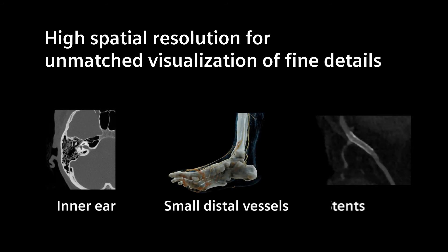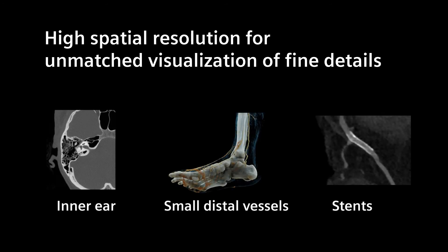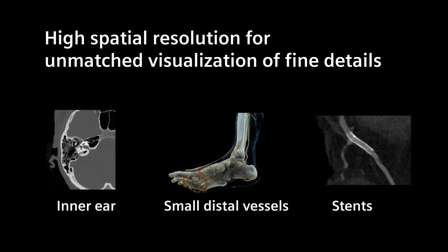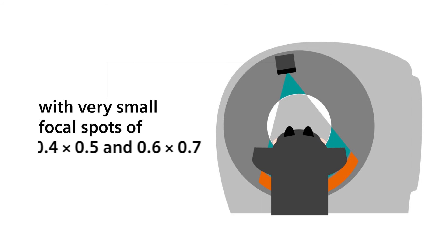For unmatched visualization of fine details, for example in inner ear imaging and CT angiography, you need high spatial resolution. That's why we designed our Vectron X-ray tube to provide very small focal spots independent of the KV, current settings, and scan duration.